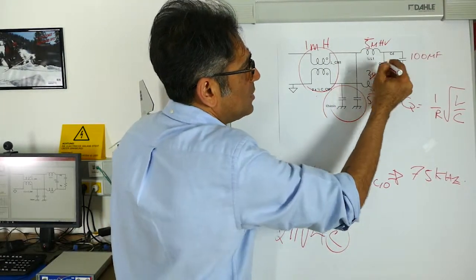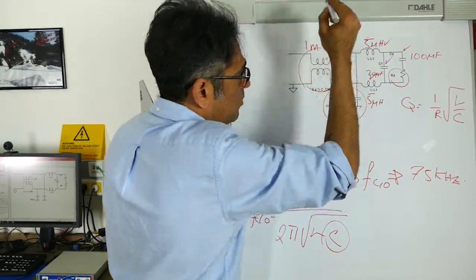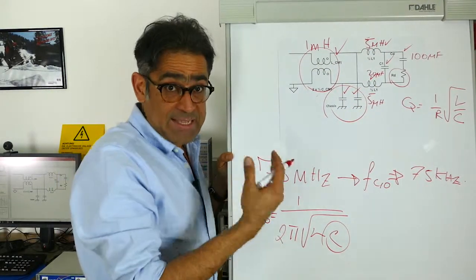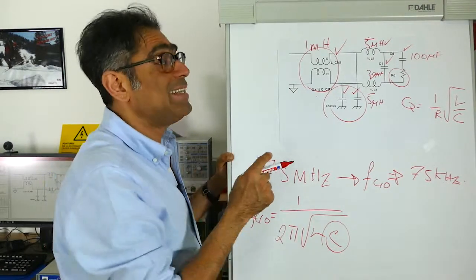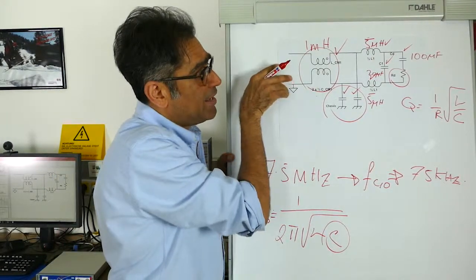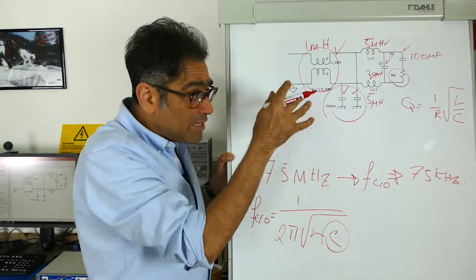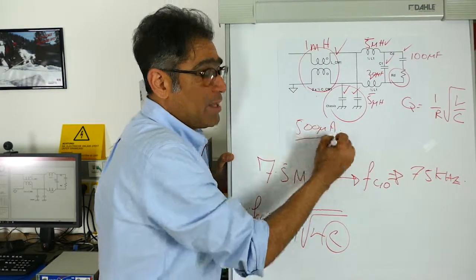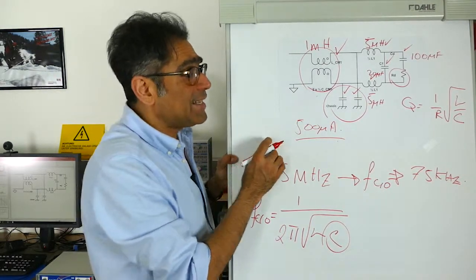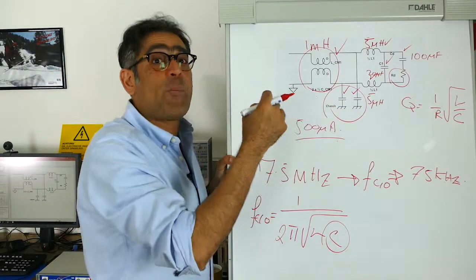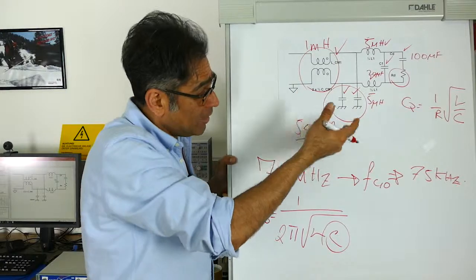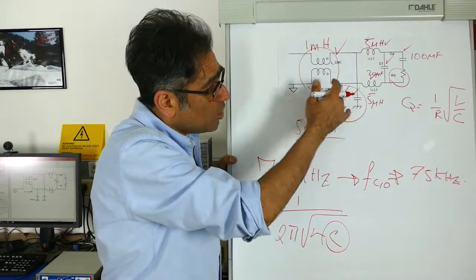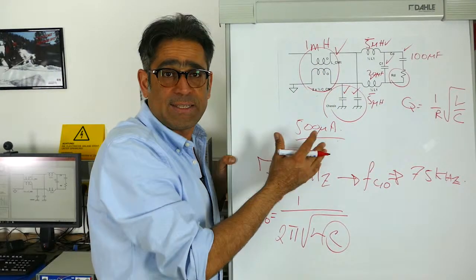So I have now calculated all of these component values and my design is complete. In the case of AC line filters there is an extra requirement because the leakage from your line and neutral down to chassis is limited — it could be, depending on the standard, 500 microamps. In that case you calculate the size of the capacitors based on how much current will flow through them, and you cannot exceed that value. That gives you the second way of calculating and ensuring these values do not violate any of the criteria.